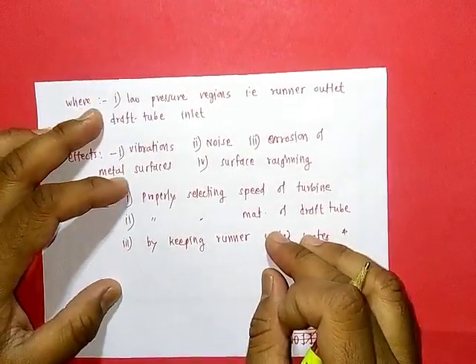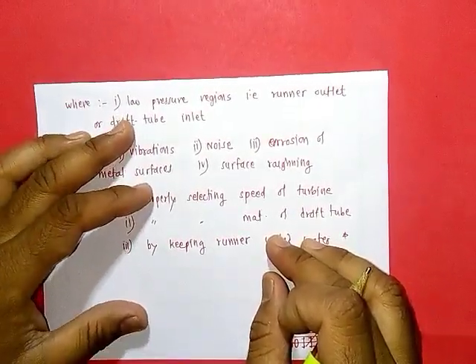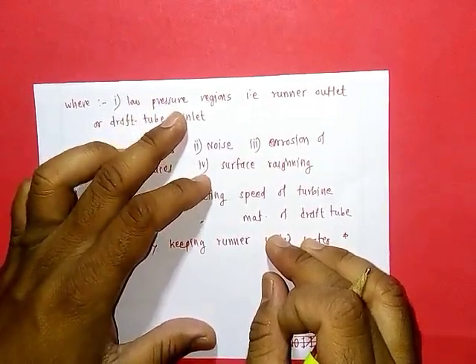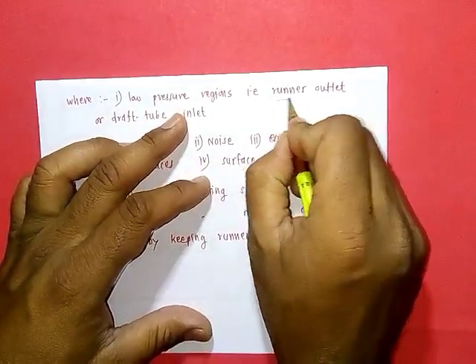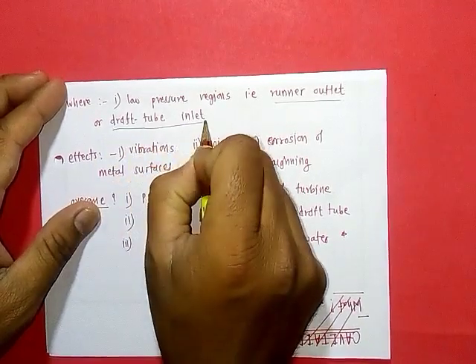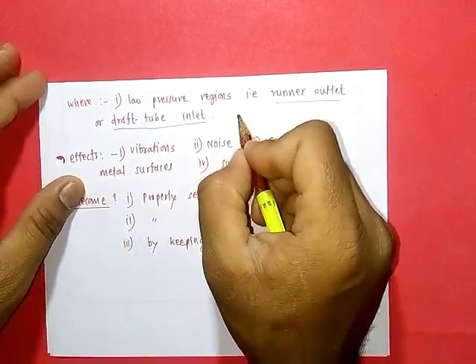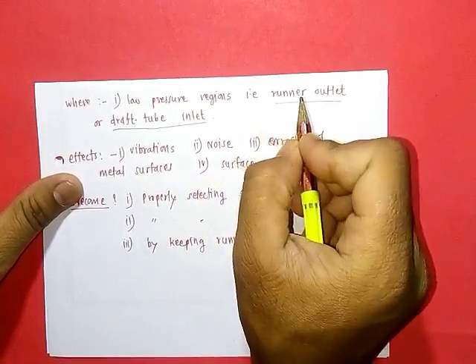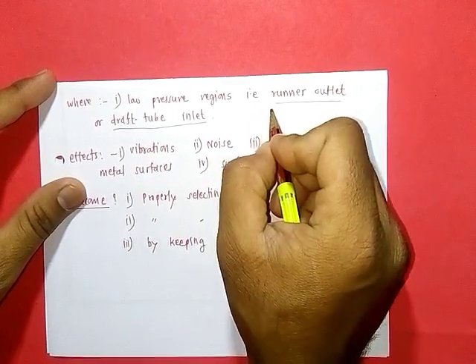These vapor bubbles are formed at low pressure regions. Within the turbine, low pressure regions are located at the runner outlet and draft tube inlet. At these two regions, when pressure drops below the saturation pressure corresponding to the surrounding temperature, vapor bubbles are formed — this is the formation step. These bubbles then grow in size.